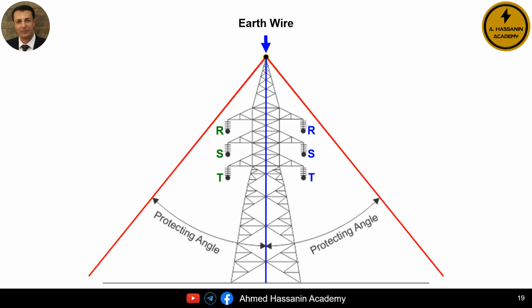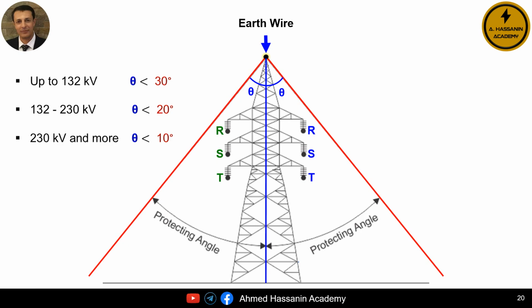Therefore, if a lightning strike hits the earth wire, it can protect the phase conductors R, S, T, and the tower insulators located within this protection angle. However, if these insulators or phase conductors are located outside the protection angle, it means that this earth wire cannot protect them. According to some research and specialized companies manufacturing transmission towers, the protection angle of the earth wire, for example, the angle theta shown here, is as follows.